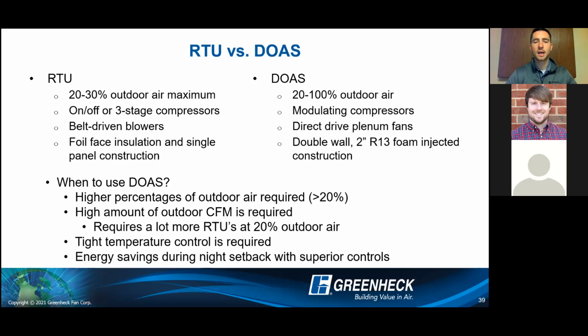And then lastly here, I want to touch on RTU versus DOAS. That is a big question right now, especially in this market. Some big differences between the two: obviously your traditional rooftop unit is generally looking at 20 to 30% outdoor air maximum. When we talk about DOAS units or think about the RVE product line, generally we're trying to size for 20 up to 100% of outside air. Are there times that we can go below 20%? Absolutely, depending on the situation there. But generally, that's what you're looking at, 20 to 100%. With RTUs, it's more so staged on/off or potentially 3-stage compressors, versus true modulating compressors with that digital and inverter technology on these DOAS type equipment.